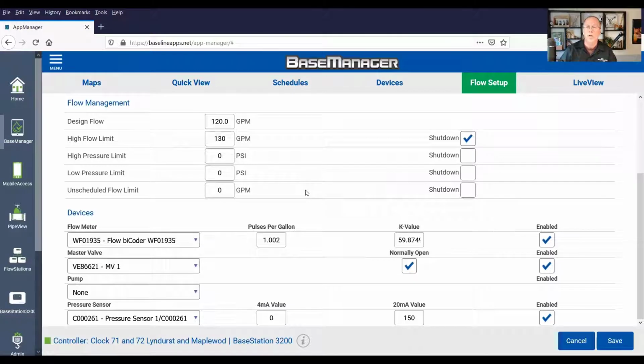When I mentioned earlier that I'm assuming they had their devices set up correctly, actually having the correct K value in here is critical because the K value is going to translate those pulses into actual GPM. If it's so many pulses and it's a 1-inch flow sensor, it'll say that's 20 gallons a minute. But if it's those pulses through a 2-inch flow sensor, it'll say that's 107 gallons a minute. So we need to make sure that the K value is accurate for the flow device that you're using. The other thing you want to look at is whether your master valve is truly normally open or normally closed. We want to make sure that those are accurate. Again, I'm assuming you've done that correctly. Get out of this one. We don't need to save this, so I'm going to cancel that one.